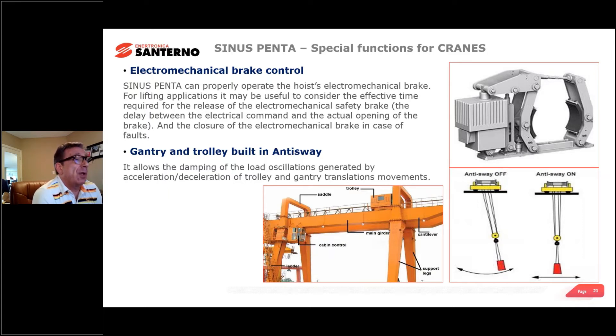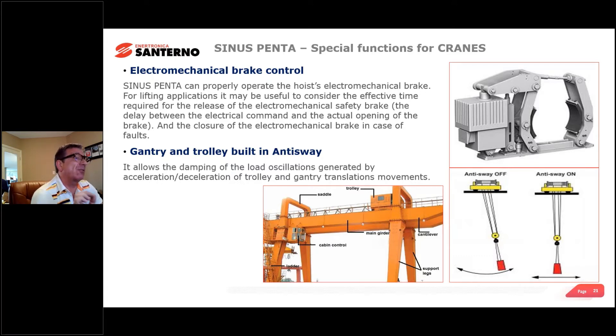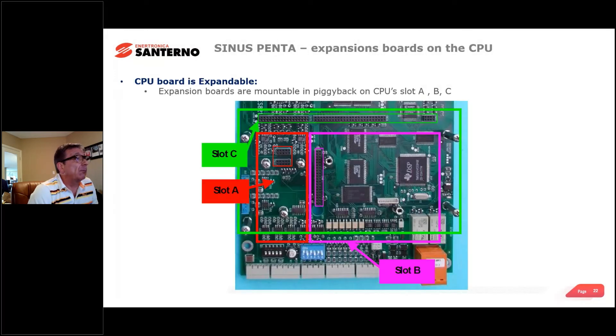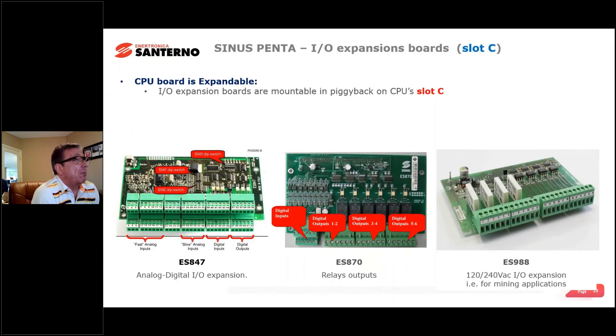For crane applications, the drive can control the actual brakes and has an anti-sway function. As the motor controls the crane up and down, it can be programmed to counteract the swaying of the load — if you're pulling on the motor you have good control and can almost counteract that sway. Your CPU should always be expandable — the main control board should have expansion slots when specifying drives.